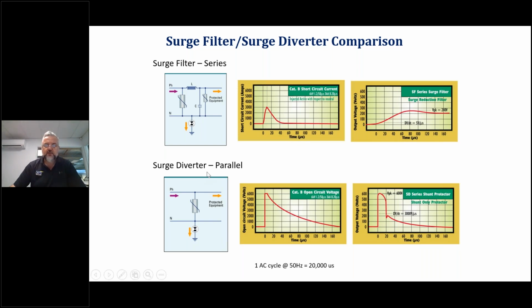Surge diverters are the most commonly used, and I will just concentrate quickly on this graph. If you don't have any surge protection and you have a surge at your EV charger, potentially your charger would see around 6,000 volts. Mind you, this 6,000 volts is not sustained voltage, it's a very short duration, only a few microseconds. But sometimes for electronic equipment, it's quite enough to cause damage, mainly due to what we call dV/dt, or fast rise time of voltage, where you can see that voltage would go from 0 to 6,000 in no time.